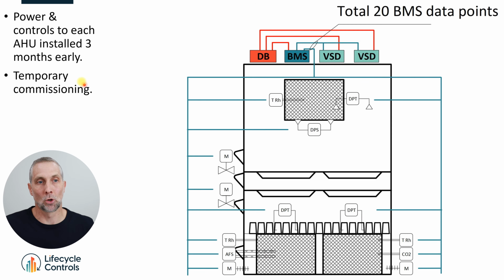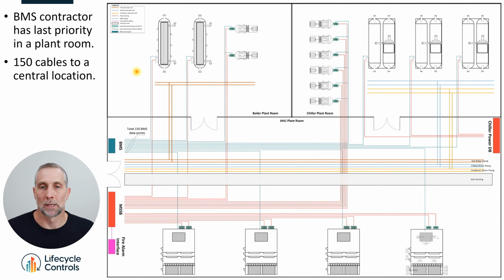Now here I've got the second dot point. It says temporary commissioning, and this is where the whole thing falls into place. If you want to do temporary commissioning in this plant room, the entire plant room has to be fully complete to power up this power board and power up these controls. The electrical union is not going to allow you to power up a plant room if there's people working all over the place.